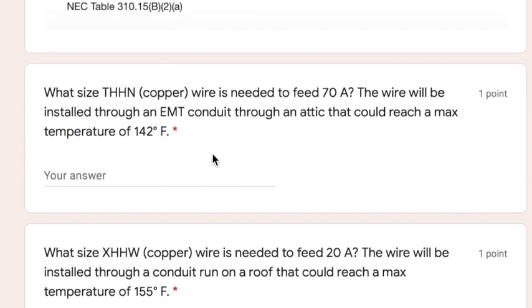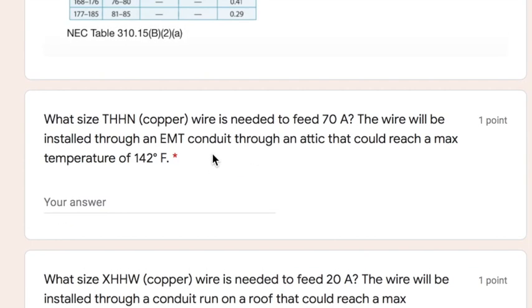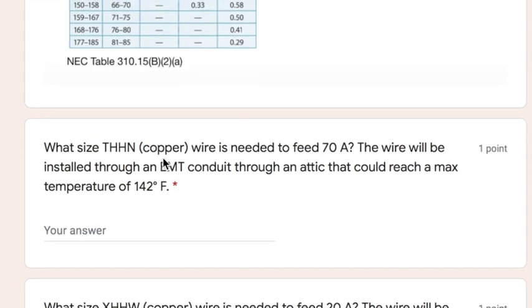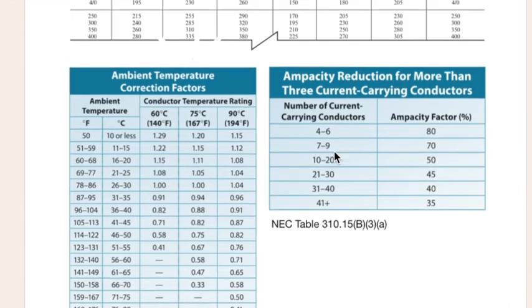First one, what size THHN copper wire is needed to feed 70 amps? The wire will be installed through an EMT conduit through an attic that could reach a max temperature of 142. So there's no adjustment factor with this because I didn't say anything about number of conductors, but I am telling you that we have to worry about the temperature. Well, it's going to be essentially the same thing we did with adjustment factor.